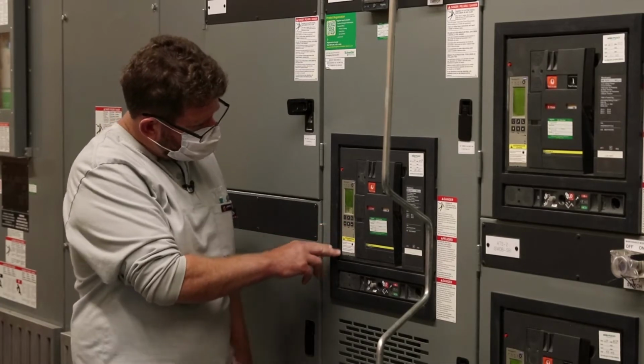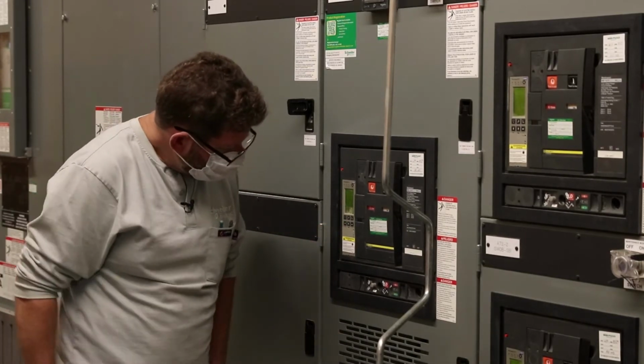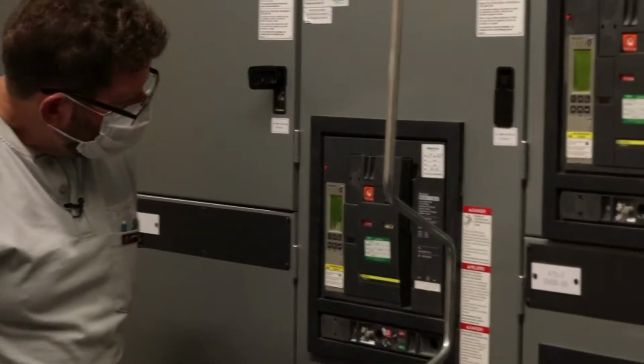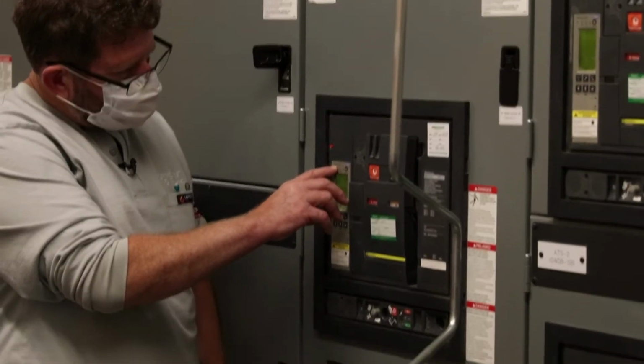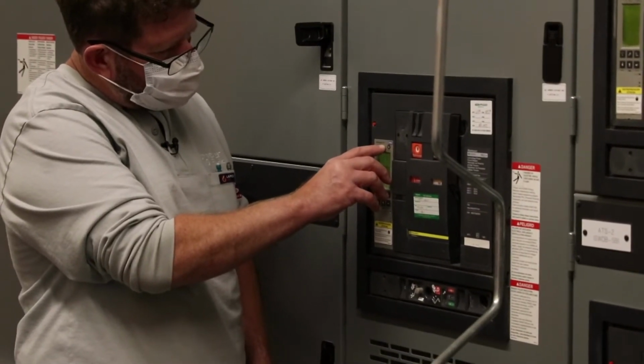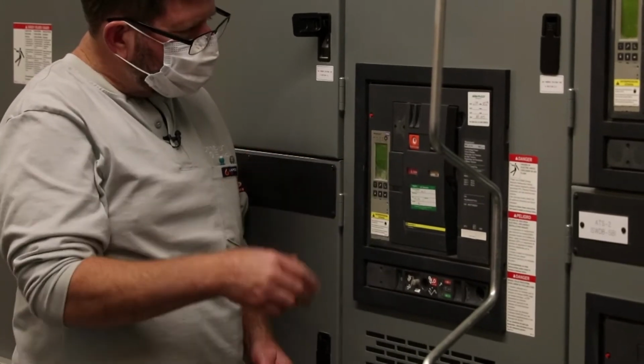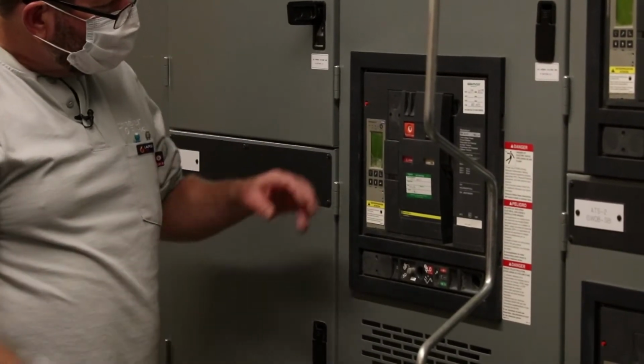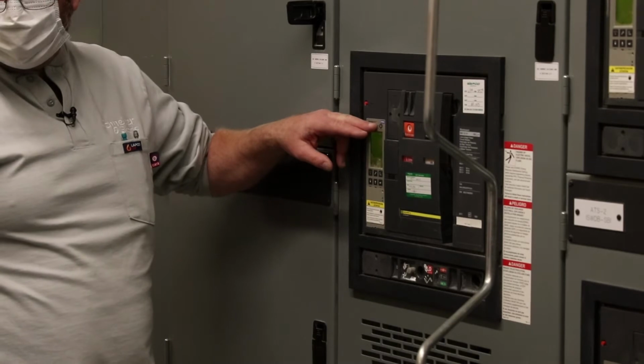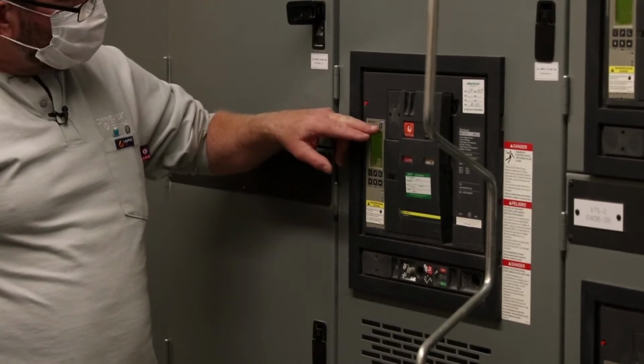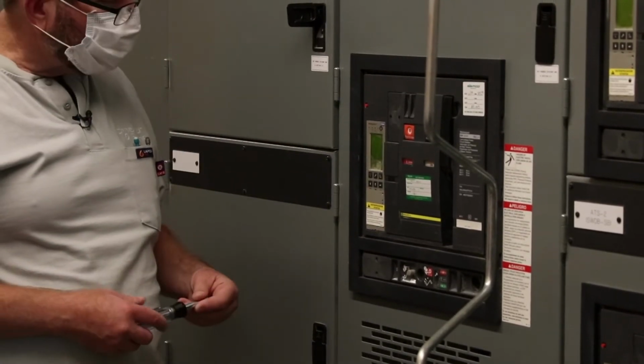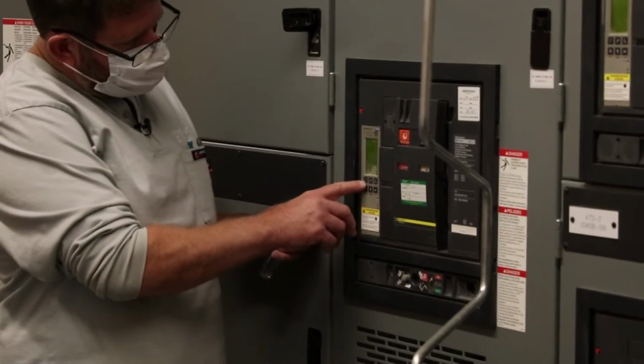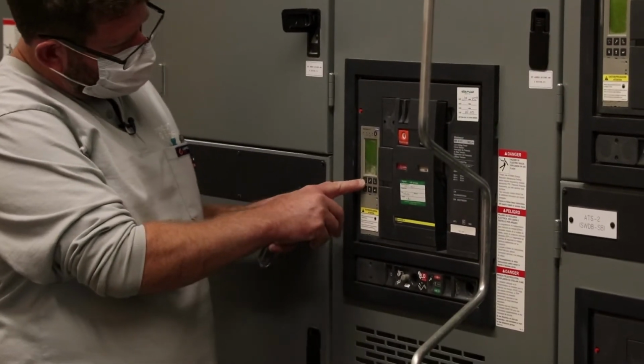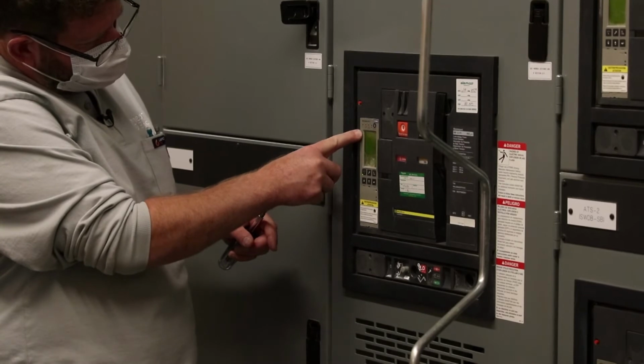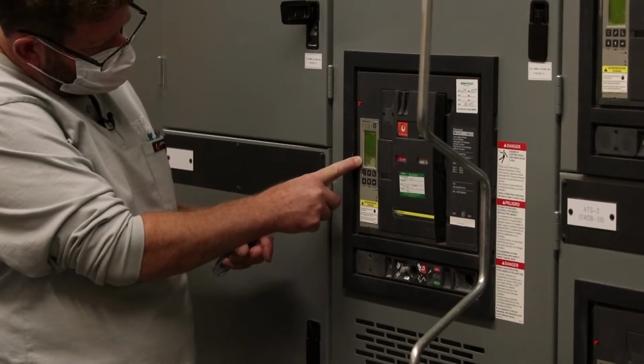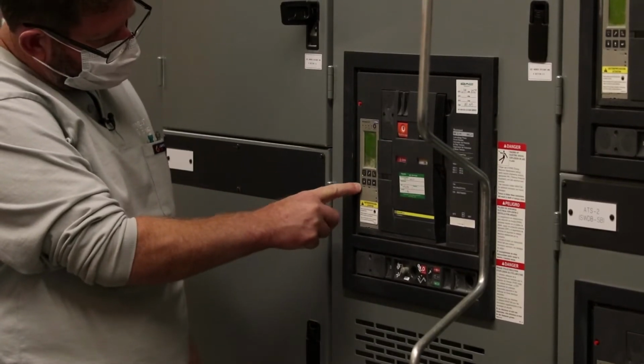And then this is a trip unit. We call it Micrologic 6.0P trip unit. Micrologic is just our name for trip units. 6.0 is telling us that it's a ground fault trip unit. And P says it's power. It gives you power readings. If you look at your meter button here, you can go in here and you could select to look at current, voltage, power, energy, or frequency.